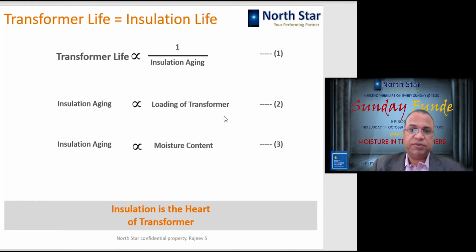Then insulation aging is proportional to the loading of the transformer, and insulation aging is also proportional to the moisture content of the transformer. So if you look at it from this angle, if the transformer is subjected to heavy moisture and is loaded heavily, then of course the life of the transformer is going to be very short. The aging of such a transformer will be quite fast, and the transformer will reach its end of life much earlier than it is designed for. Okay, so we can say that if the insulation fails, the transformer fails. That means the insulation is the heart of the transformer.